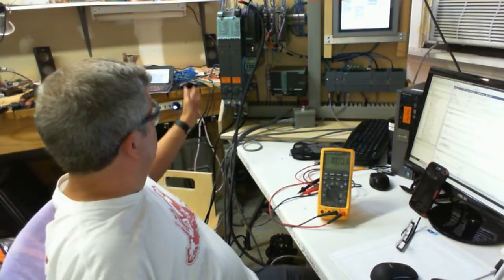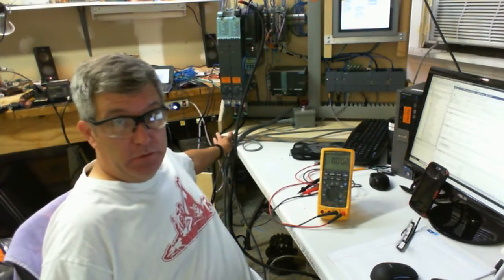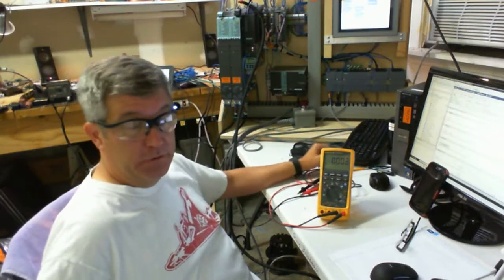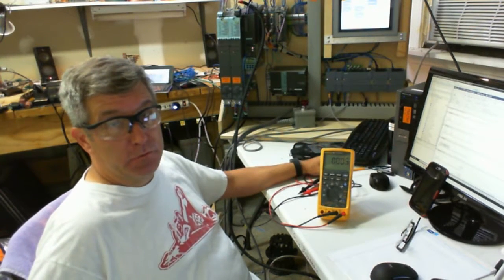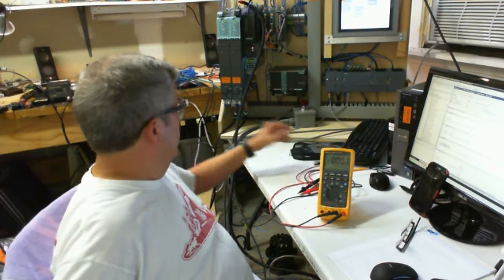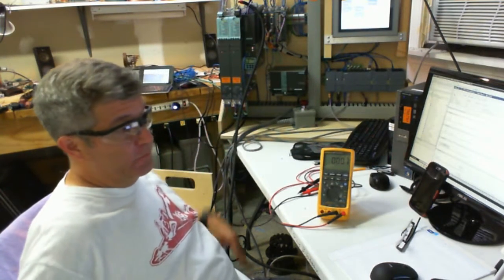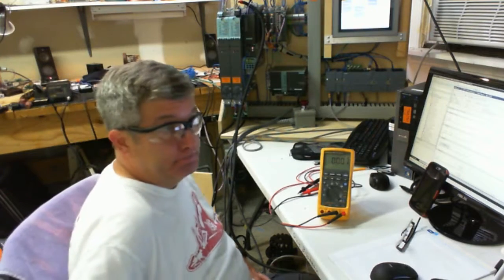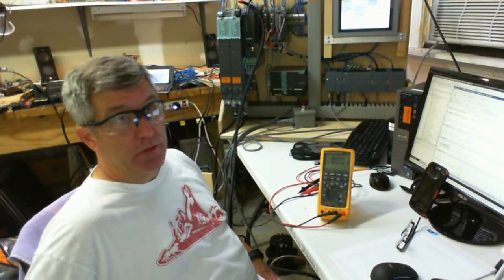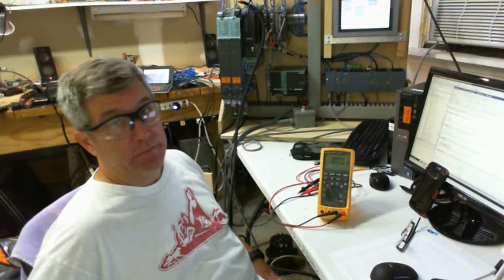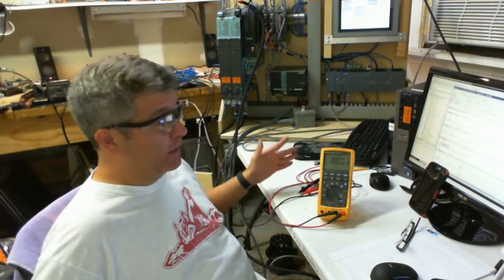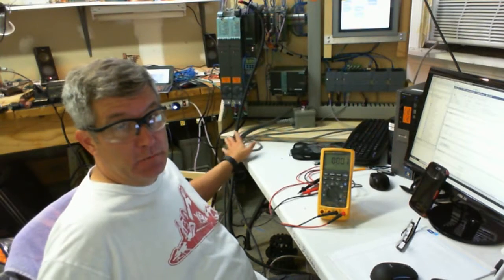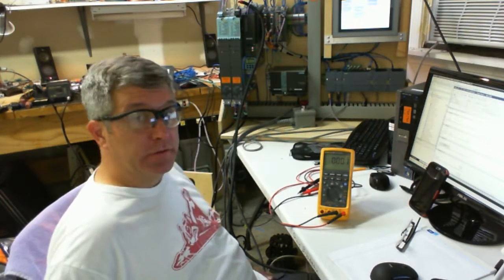You can't handle any of the leads, the output leads to the motor, anything, until you've measured that the voltage is down to a few volts. The outputs to the motor are three phase. There shouldn't be voltage on them, but if you have a damaged transistor, there can be. So even right now, with just a DC bus charged, if there was a damaged transistor and I went messing with the motor leads, it could kill you.